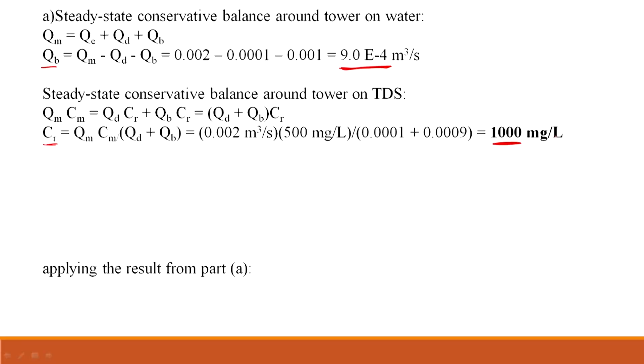What would be the minimum possible makeup flow, and what would be the concentration of TDS in the blow down or the recirculating water at that makeup flow? We will look at why we need blow down in these evaporating towers later. But as you see, you can never rule out evaporation or drift, that is the whole purpose of a cooling tower, but you can stop blow down. So the minimum makeup flow will equal the loss of water due to evaporation and drift. Q minimum equals Q evaporation plus Q drift, when Q blow down is 0.